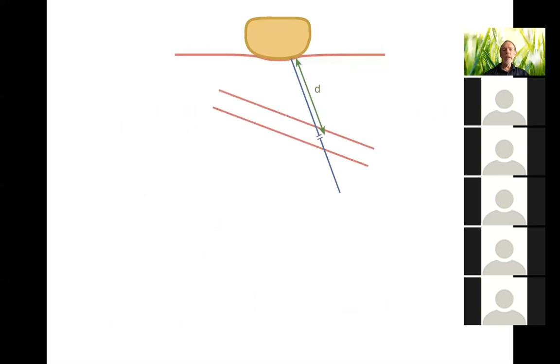So graphically, here we've got the setup of a pulse Doppler measurement. You've got a blood vessel. You've steered the beam in an appropriate direction so that you're going to end up with a Doppler angle of less than or equal to 60 degrees. And you've set your sample volume in the center of that vessel.